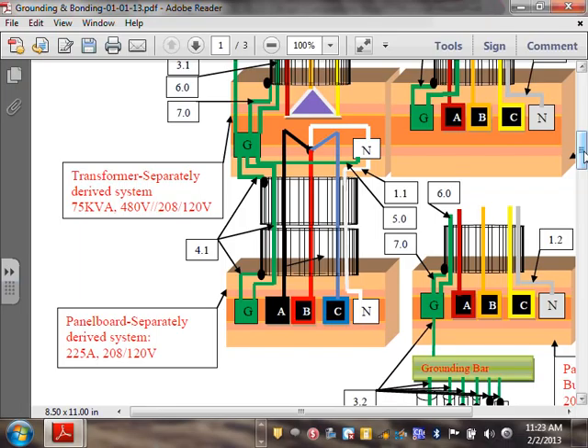I created my neutral. What if you're feeding three different panels coming out of the transformer? Then, if you're bonding inside the transformer, it has to be based on all the feeders that are feeding all these panels. Or you bond inside the panel, and then you don't have to worry about that. So if there are three panels, 250, 225.